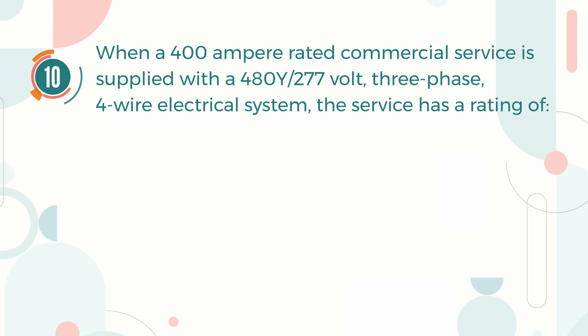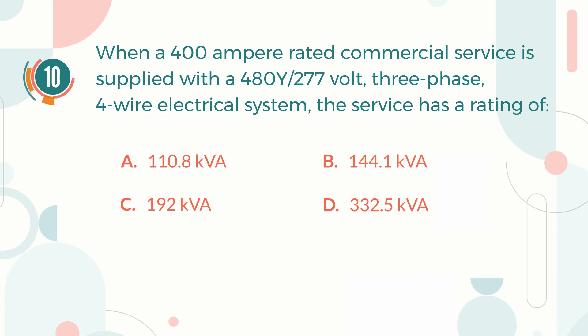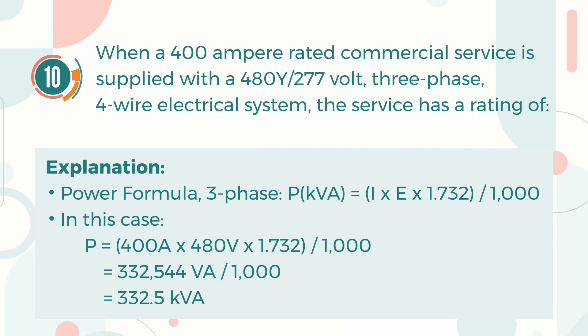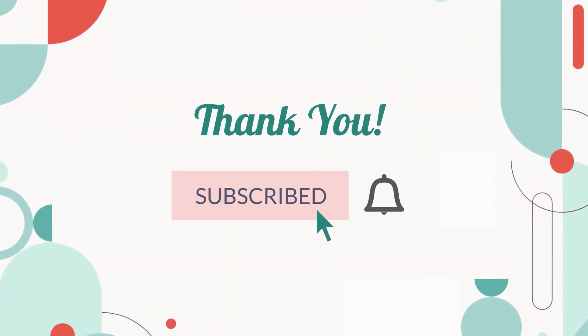Number ten: When a 400 ampere rated commercial service is supplied with a 480Y/277 volt, three phase four wire electrical system, the service has a rating of — A) 110.8 kVA, B) 144.1 kVA, C) 192 kVA, D) 332.5 kVA. The correct answer is D, 332.5 kVA. We apply the three phase power formula: kVA equals 1.732 times the multiplication of current in amperes and voltage in volts, divided by 1,000. Power equals 1.732 × (400 × 480) ÷ 1,000, giving the answer of 332.5 kVA. Thanks for watching — don't forget to like, share, and subscribe to our channel for updated videos every week.